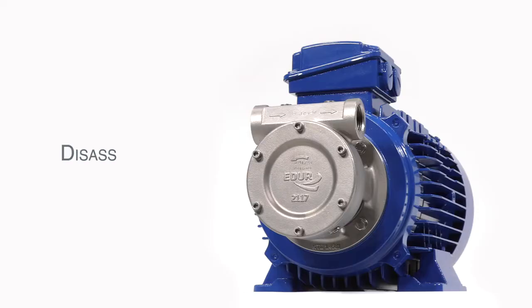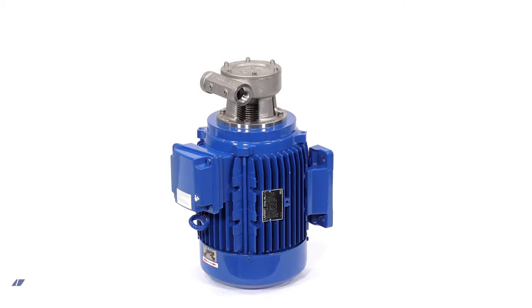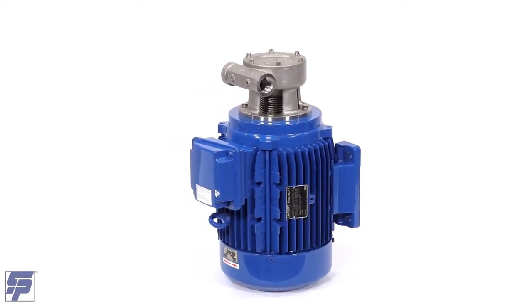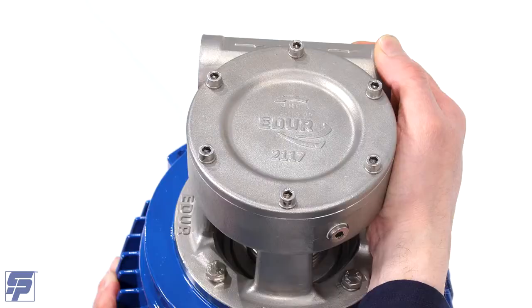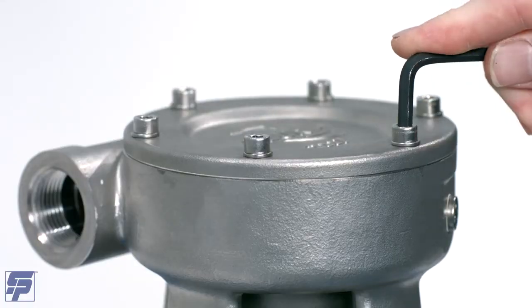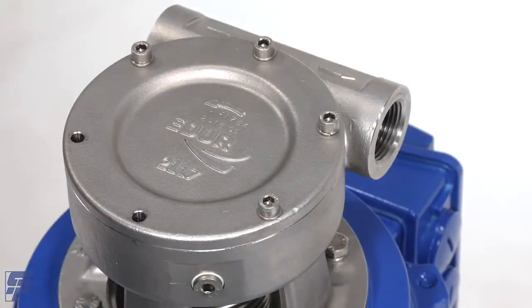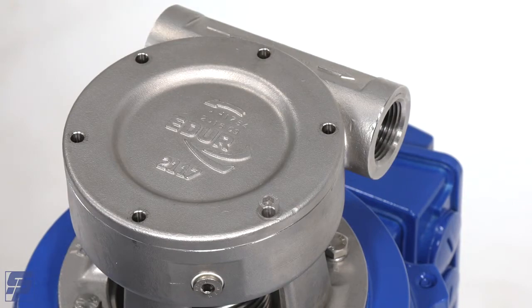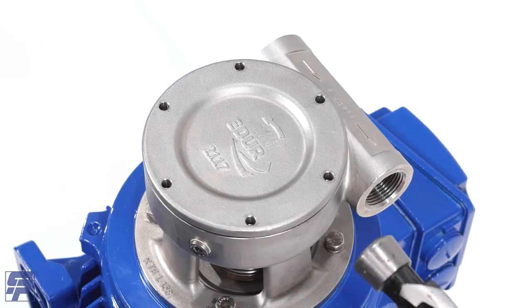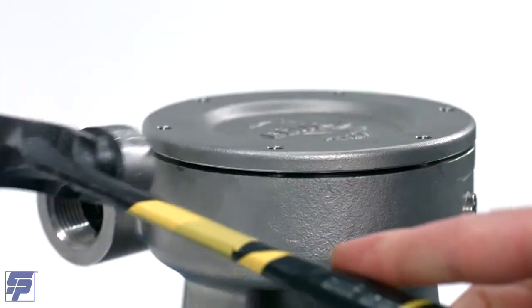EDUR PBU Disassembly. Set the pump on a workbench vertically with the motor on the bottom and the pump foot facing you. Remove the six bolts and washers with an appropriately sized Allen wrench. Remove the pump casing cover from the casing, tapping gently with a hammer if it remains stuck.